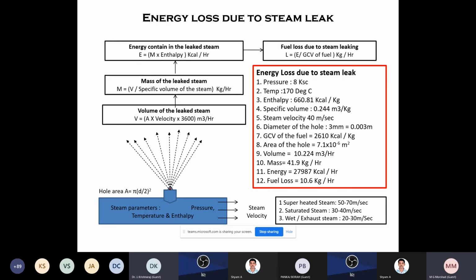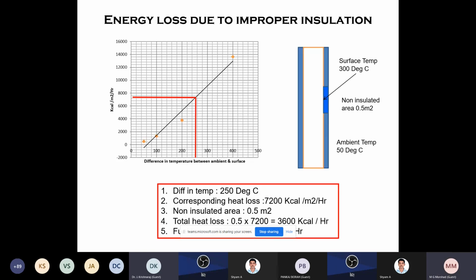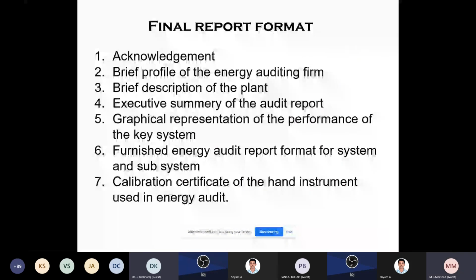Then the steam losses or other steam leaks are there. So you can also have calculations accordingly. If you have this, automatically you will be able to control. Then the insulation losses. Nowadays the thermal imaging camera is available. You take the photograph where there is a peeling off of insulation, and you give the calculation accordingly, and it will show this much energy loss will be there, or the fuel loss will be there due to dispatching. Okay.